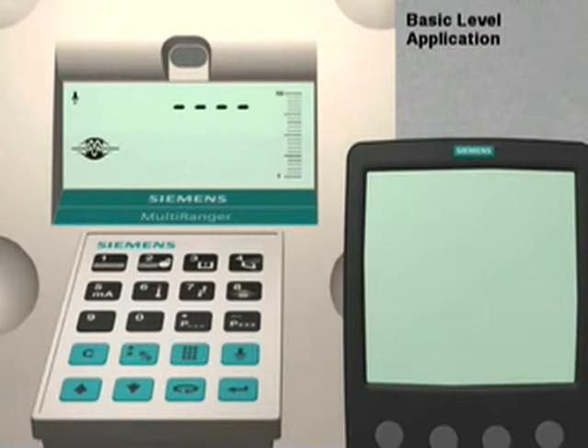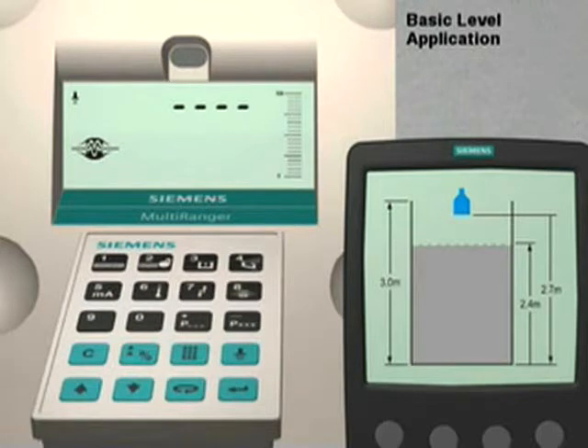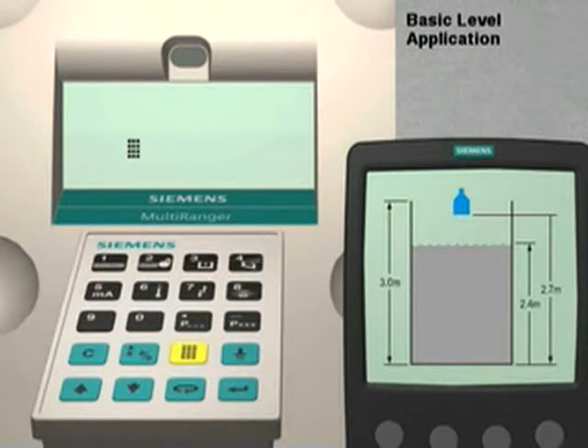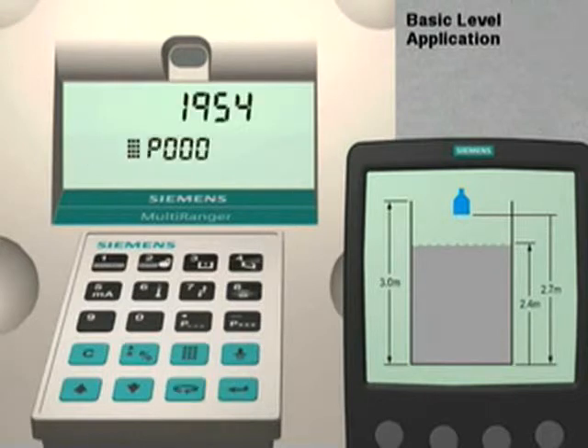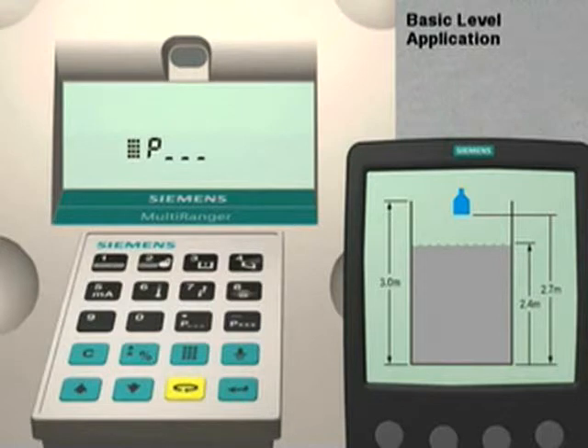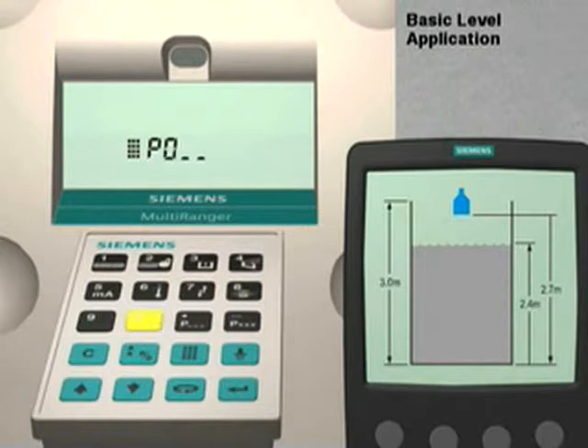We are going to set up a simple level application using the seven quick start parameters. For our application, we are going to use a multi-ranger to measure the level of liquid in a 3-meter high storage vessel. The first step is to put the multi-ranger into program mode. Push the Mode key, then the Next Display key twice until the multi-ranger displays P dash dash dash. We then enter 001 for parameter number 1.